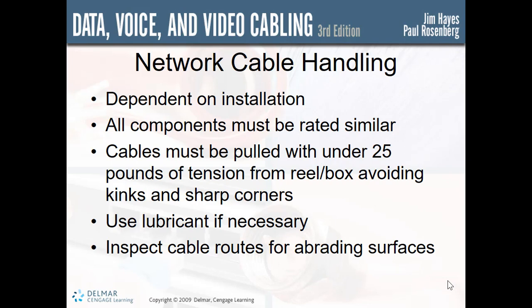General guidelines when you're doing your installation: all components must be similarly rated for performance. Cable must be pulled from the reel or box without kinking. Cable must be pulled with less than 25 pounds of tension. Use cable lubricant if conduit is necessary. Cable must not be pulled around sharp corners or kinks. Inspect the cable routes for surfaces that may abrade the cable, which means that may scratch or cause damage to the cable.